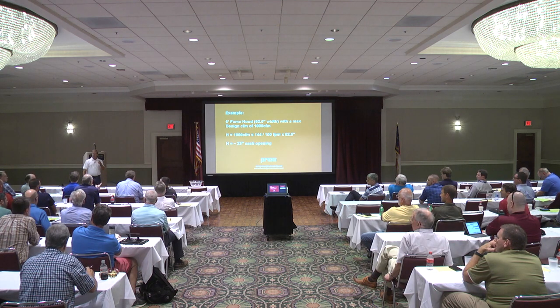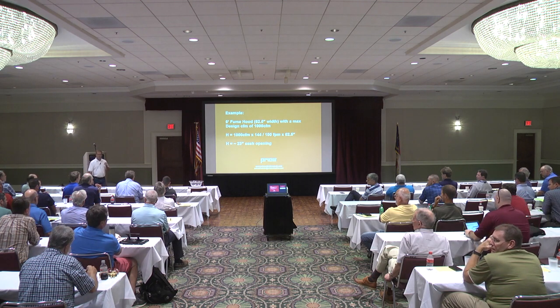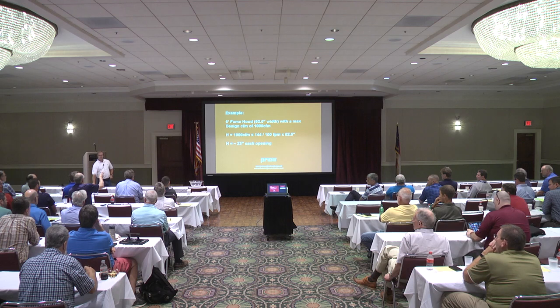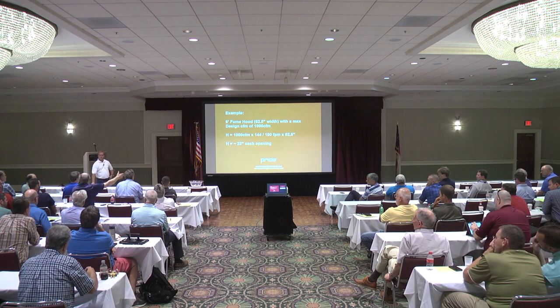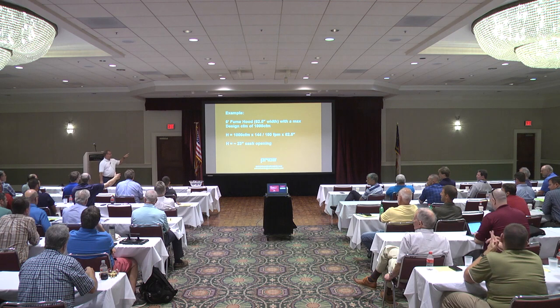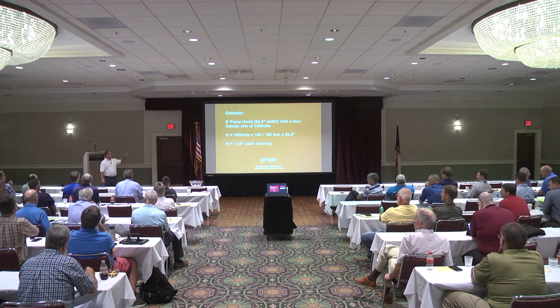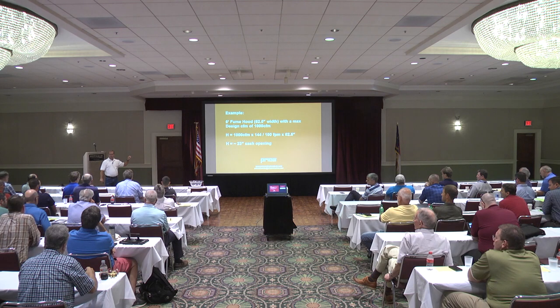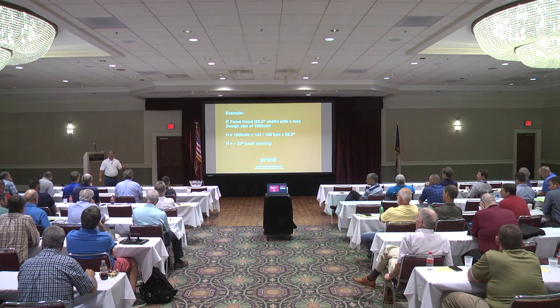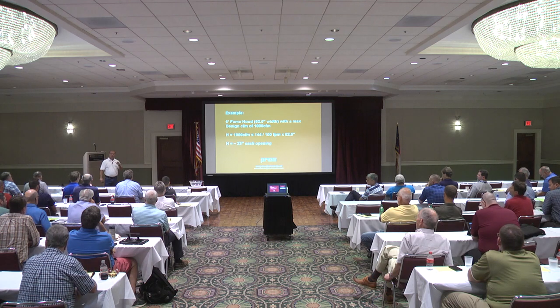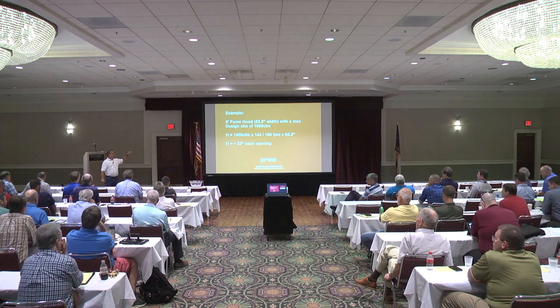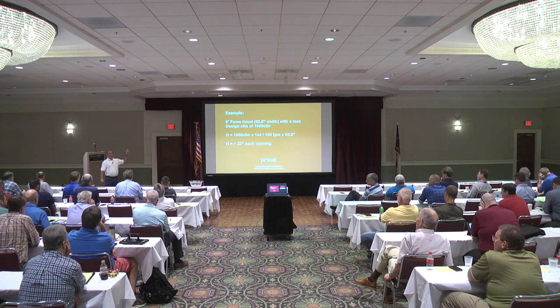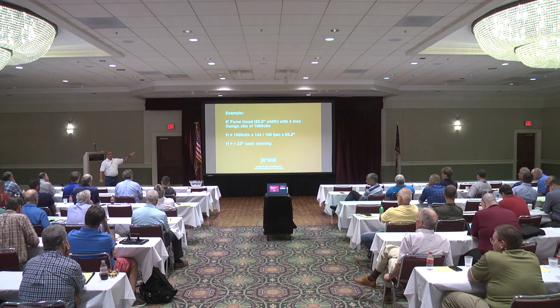You did, but I think that's assuming 100 feet per minute. And the engineer, how do we know, as test and balance professionals, that the 1,000 CFM isn't at 18 inches and 125 feet per minute? Because, again, I'm assuming that the contract documents told us 100 feet per minute for the fume hoods as a blanket velocity, variable volume, 100 feet per minute, but my top end of this fume hood is 1,000 CFM. So the only way you can get to that with those parameters, 100 feet per minute design and 1,000 CFM design on a 6-foot hood, is to raise it 23 inches.